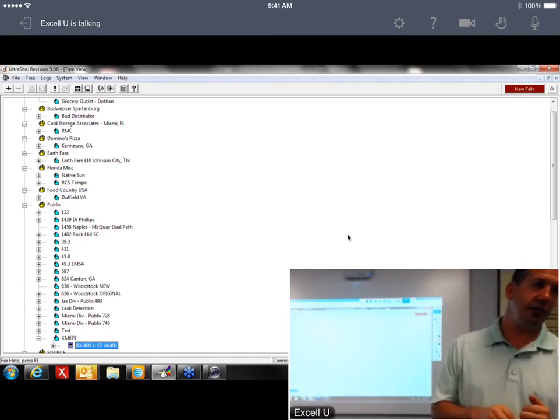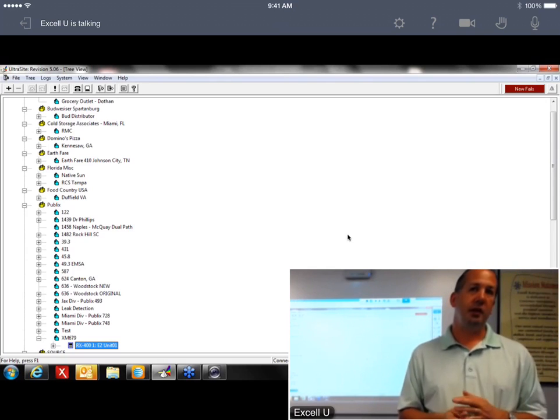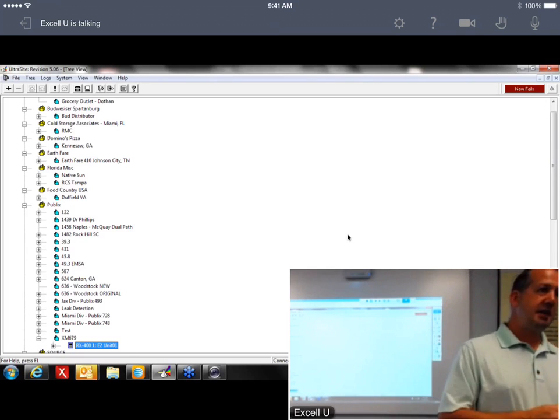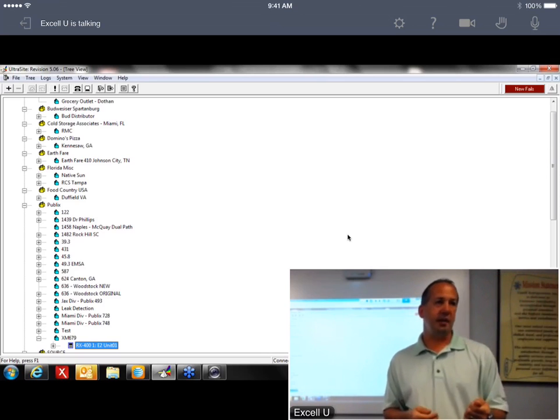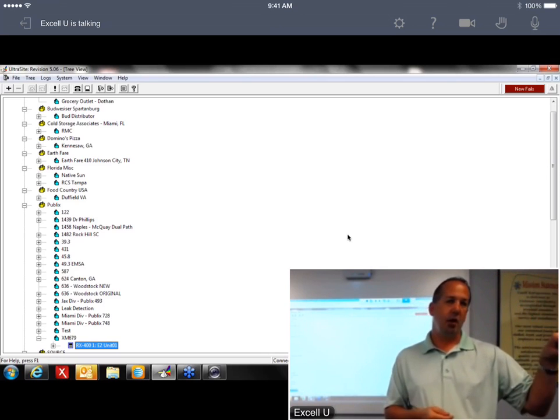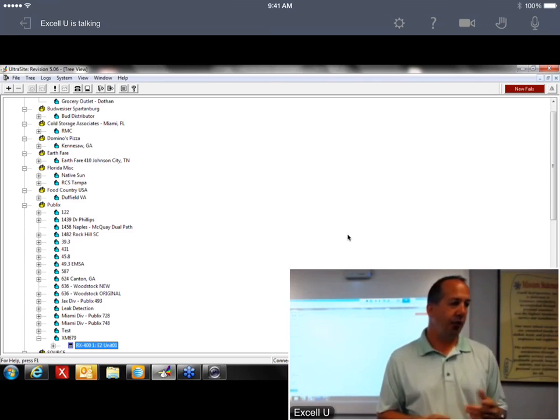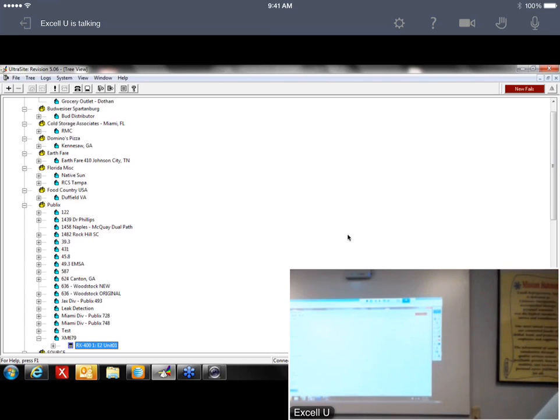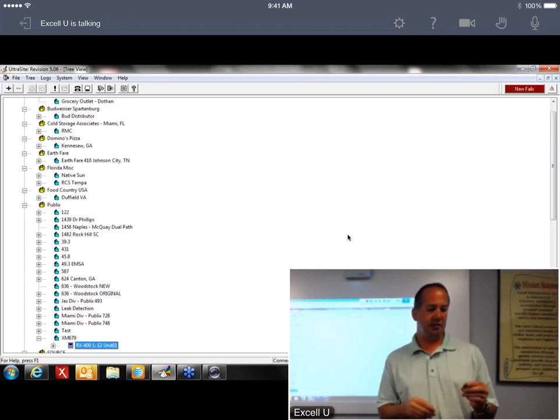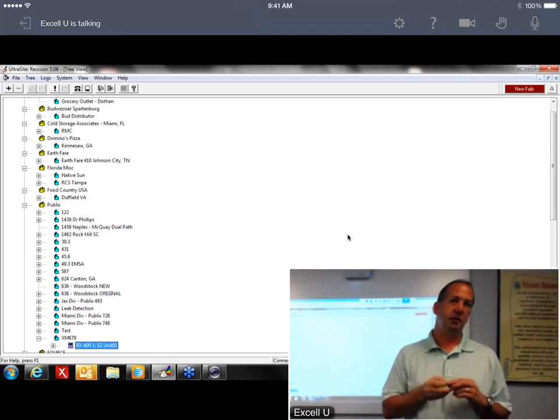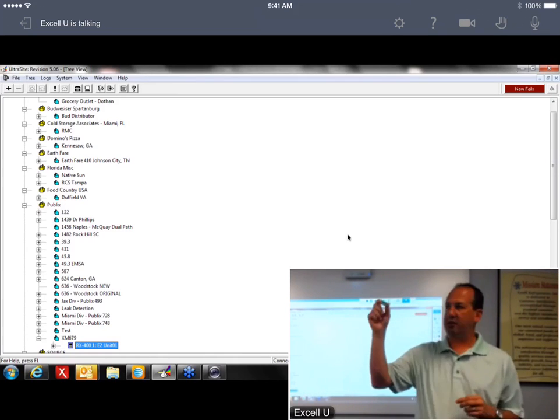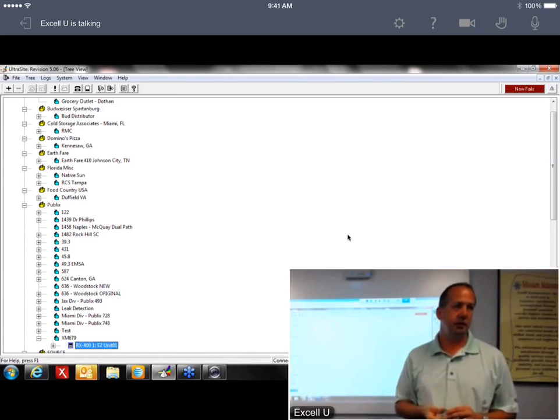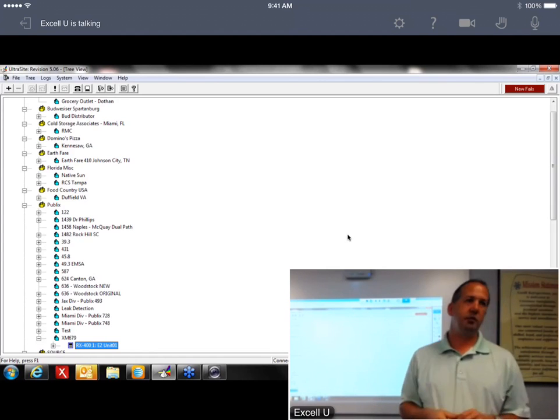A lot of the temp probes off of the old case controllers that we carry on our trucks aren't the same sensors. They had Molex connectors on the CC100s. With the Dixells, what you have is a Phoenix connector. So you can cut the Molex connectors off and feed it into the Phoenix connector. This is what goes on the Dixell Phoenix connector. You just plug the wires into here. And also the little copper loops that hold them to the suction, you can use regular CPC sensors. Yeah, the connectors to hold it.